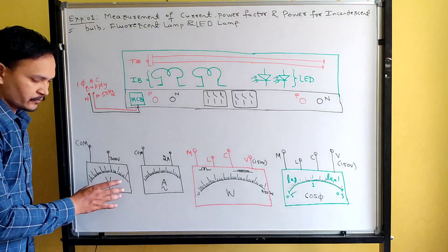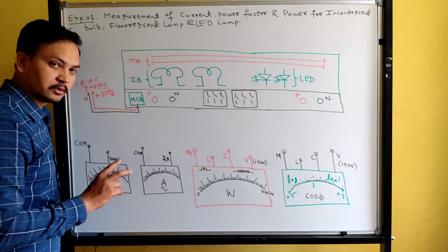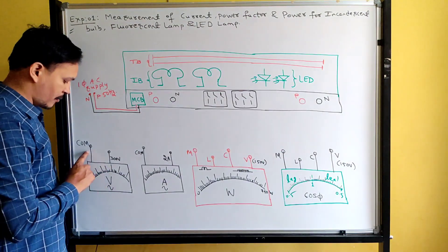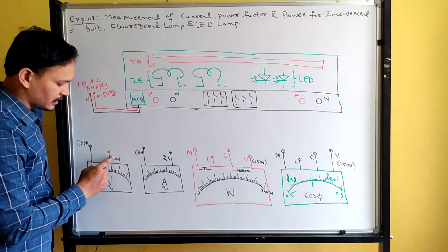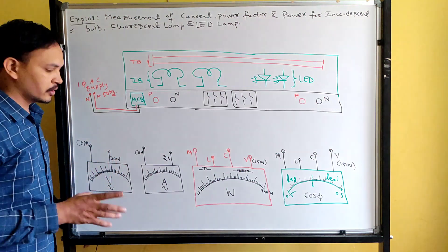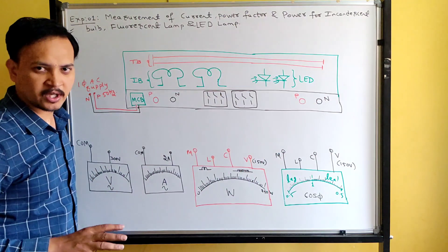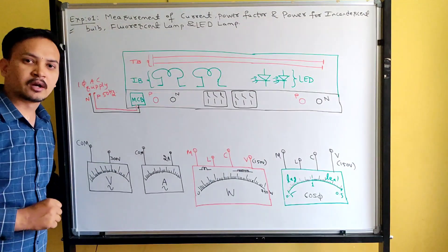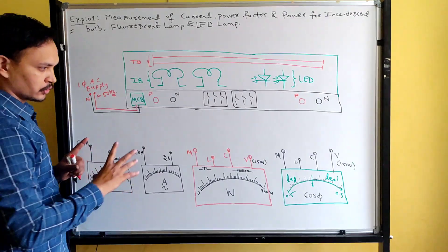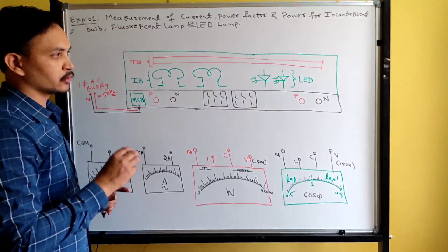Don't connect the 600 volt terminal on the voltmeter. Since we are working on single phase AC supply, select the 300 volt range. Now, please observe carefully how to do the connections, how to switch on the loads, and how to take readings.